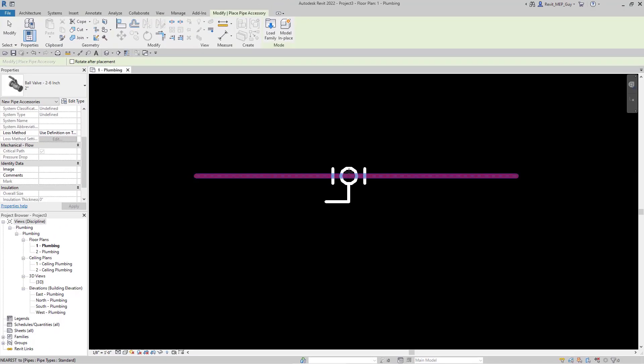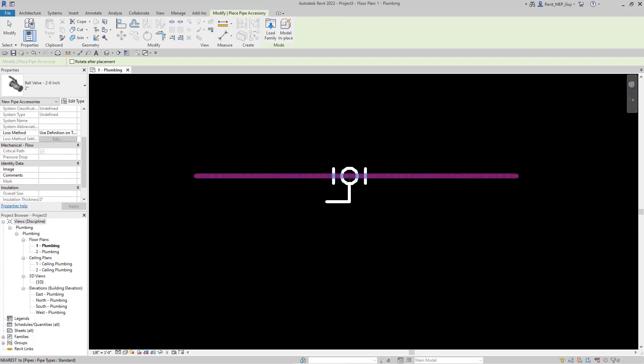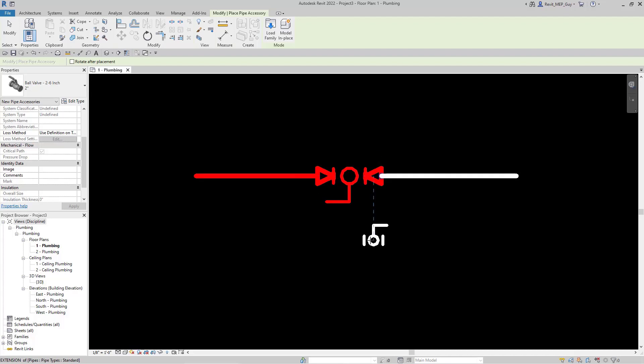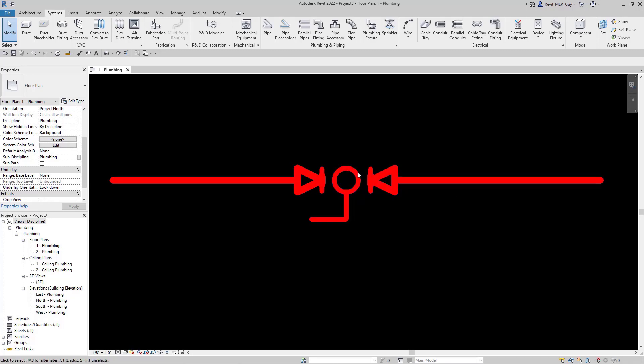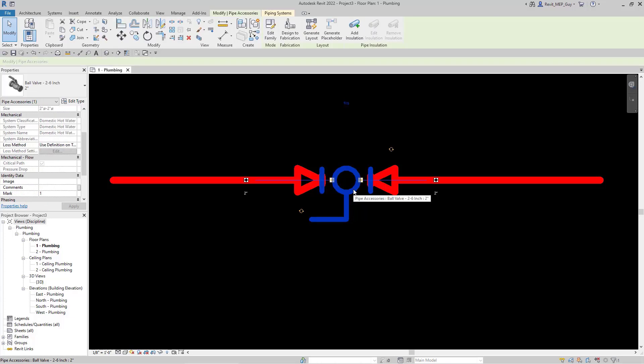Now Revit's loaded the ball valve, so let's go ahead and put it on our pipe. When I hover over it, it snaps to the piece of pipe, so I'm just going to click right here, and hit escape to get out of the command. Now we see this ball valve, but we also see these little triangles — those are increasers, and what this is telling us is our piece of pipe is decreasing in size to make this ball valve work. If we click on the ball valve, it is a two inch ball valve.